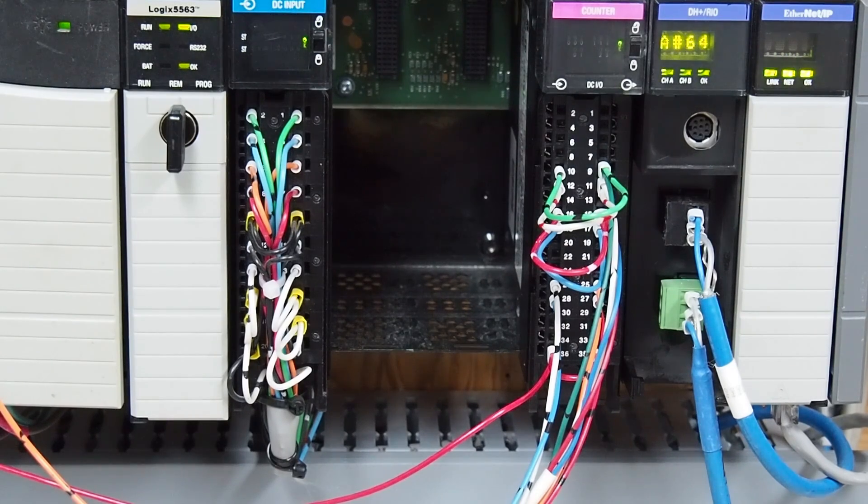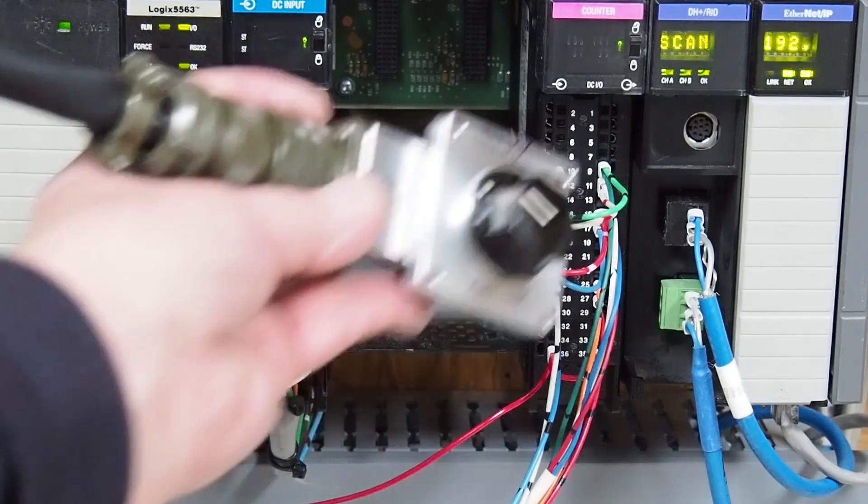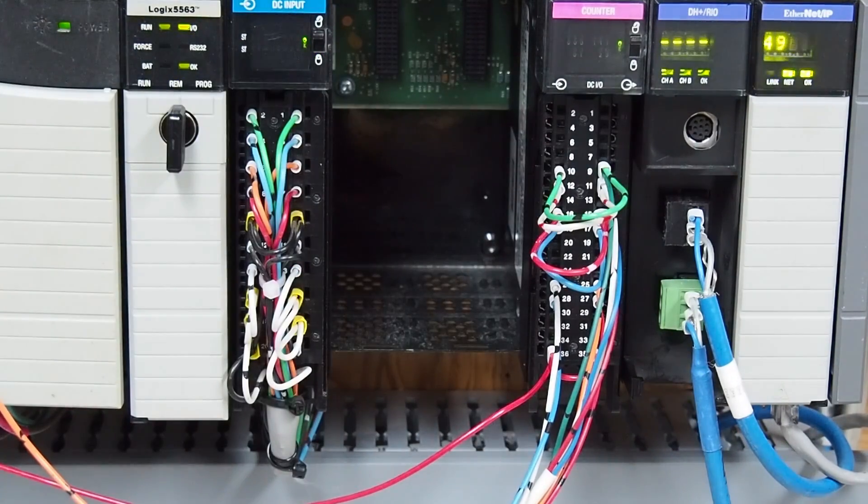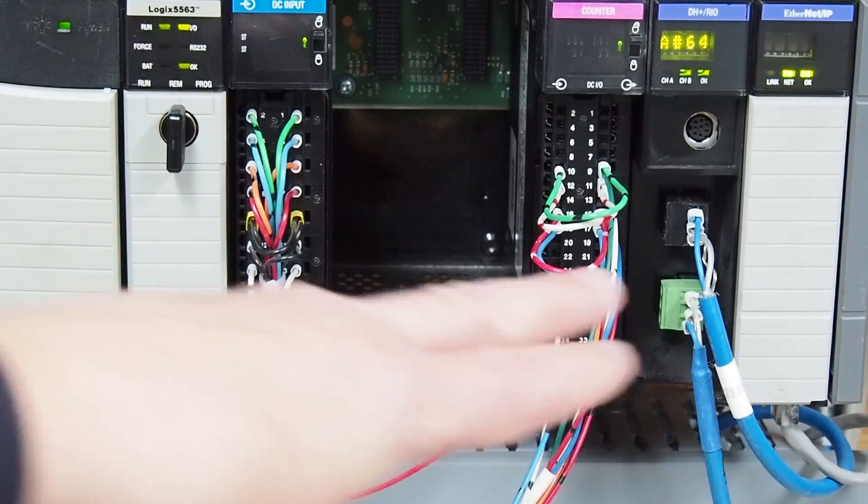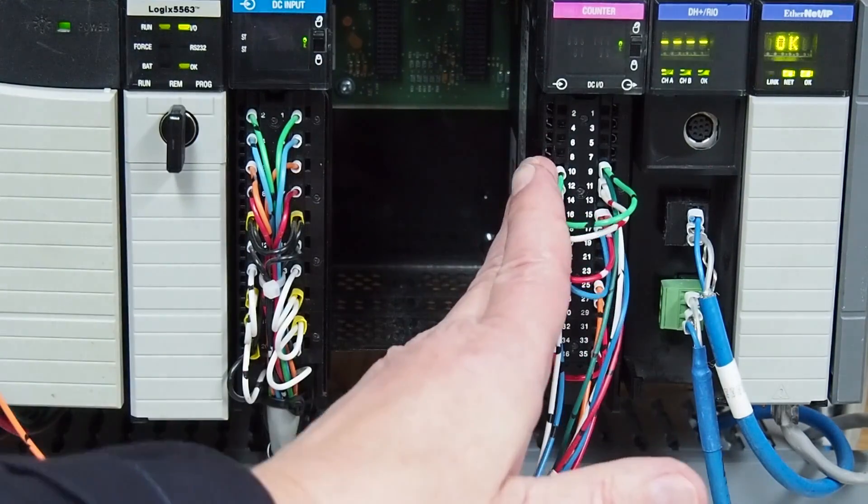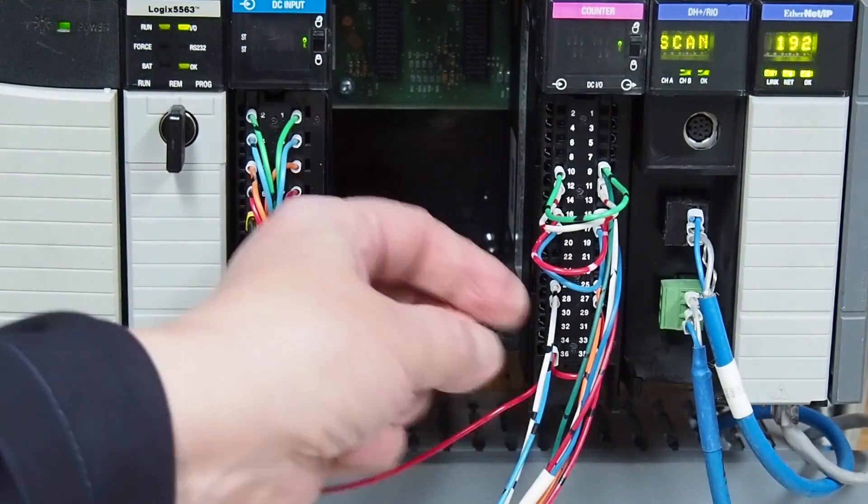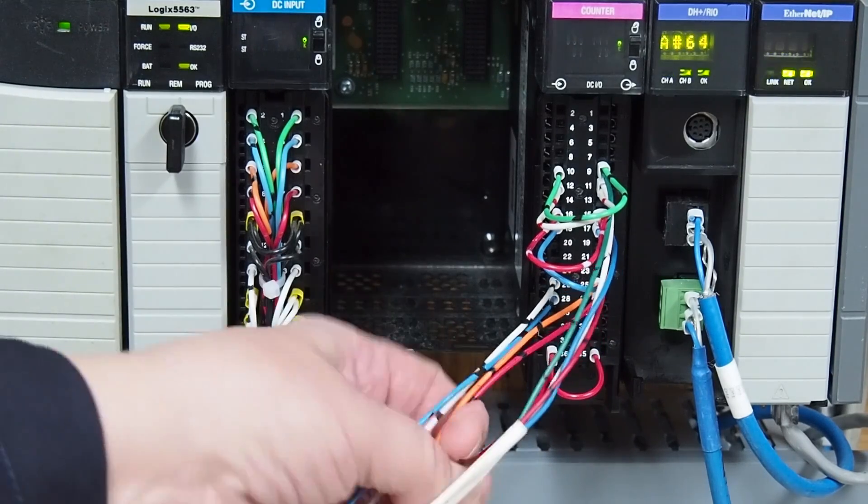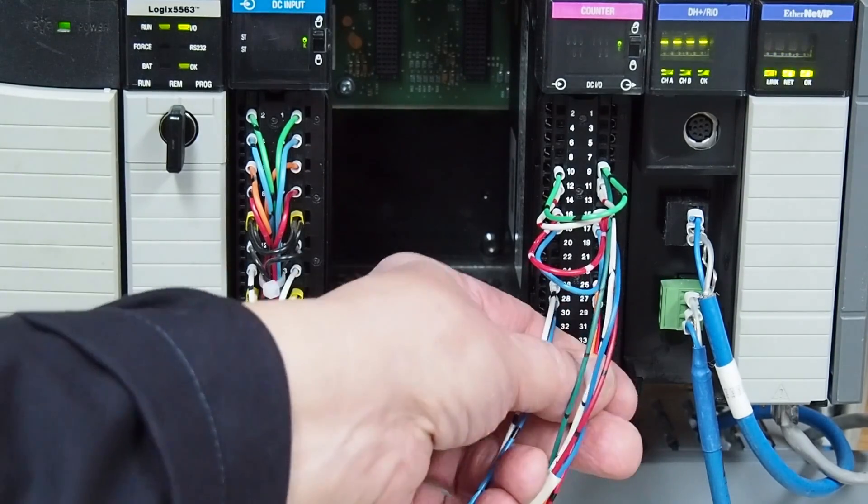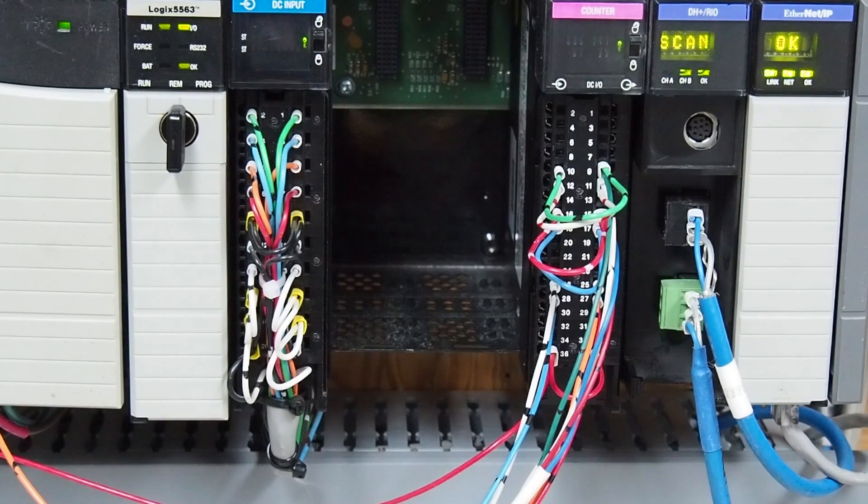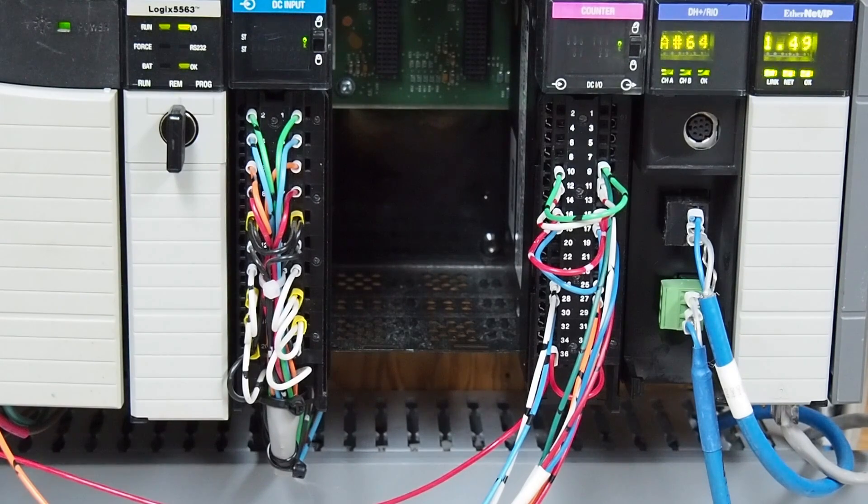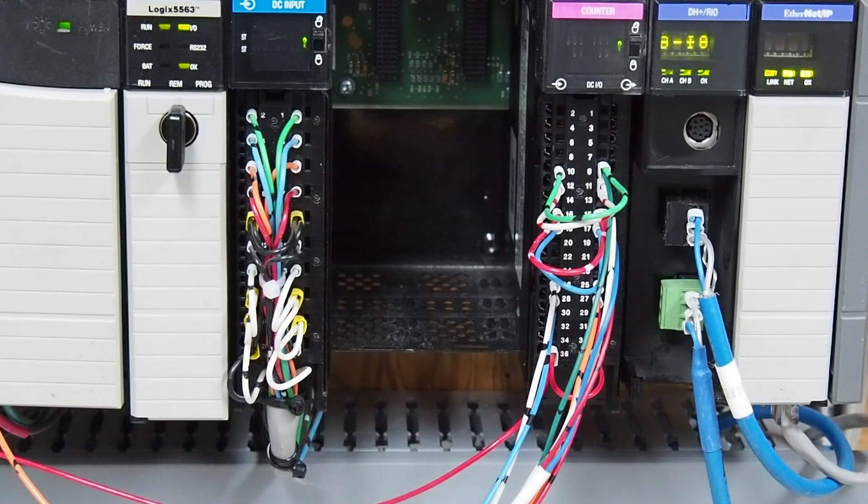Now this is an experiment I tried. I have one encoder only. And the wiring is paralleled into both channels. The four outputs at the bottom with 24 volts to turn on the pilot lights is all independent. So yes, this is a question I always had. Yes, you can run two channels with one encoder.